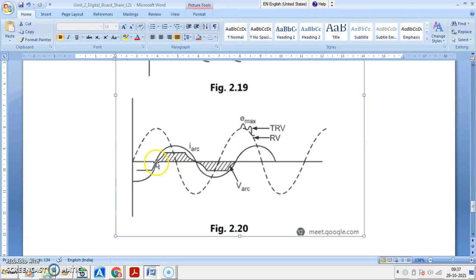आता power factor 0 म्हणजे इथे 0 होईल तुमचं, म्हणजे it will get shifted to 90 degree. Current 0 position will get shifted from this position to this position. So cos 90 काय, cos 90 0 na, so power factor will be 0 here, so lagging 0 power factor of the circuit, so peak voltage will be max. इथे दिसतंय तुम्हाला peak voltage is E max, okay, across the circuit breaker contacts, and the sudden application of this peak voltage may disturb your arc quenching process. Sir, difficulty will be there in arc extinction.